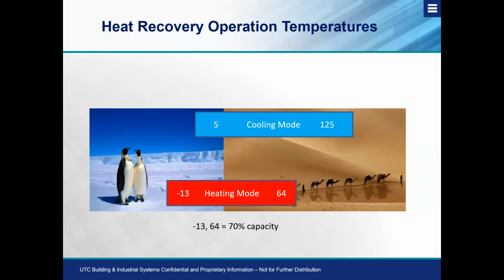Again, 100% capacity will determine whether you're dealing with a single base rail, a mid-size base rail, or a large base rail unit, or a small, medium, or large cabinet. Again, it all depends on coil surface area and the amount of compressors that we have in the outdoor units for redundancy and also low ambient heating capabilities. But on average, if we look at a 6-ton system at -13, we're going to give you 70% of that unit's rated capacity at -13.